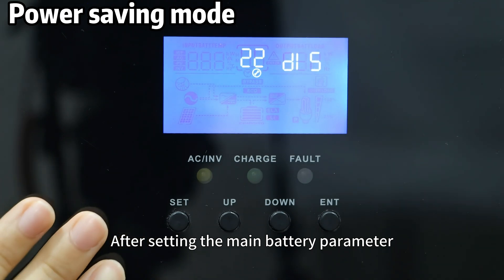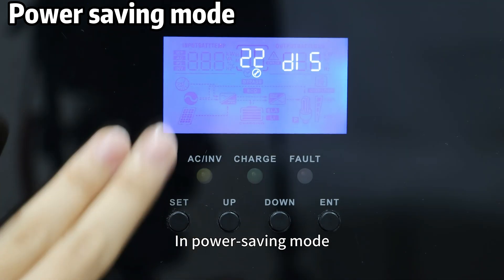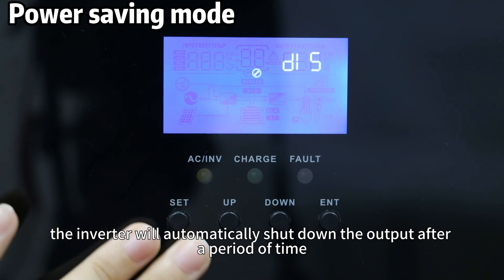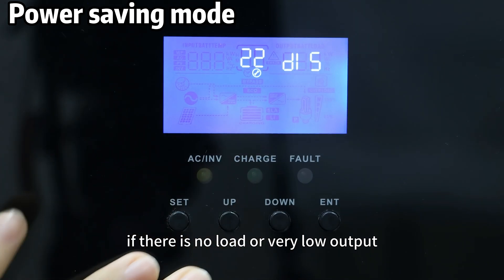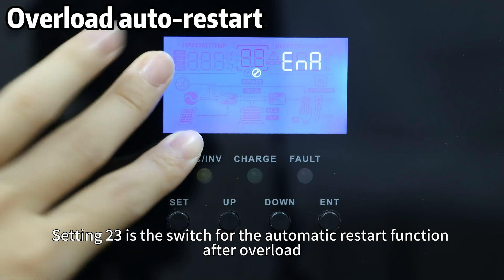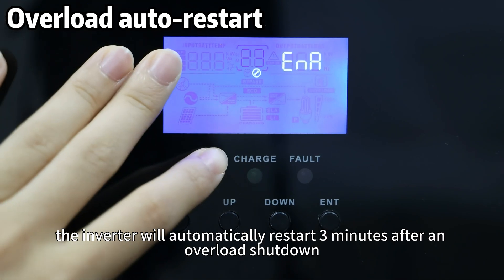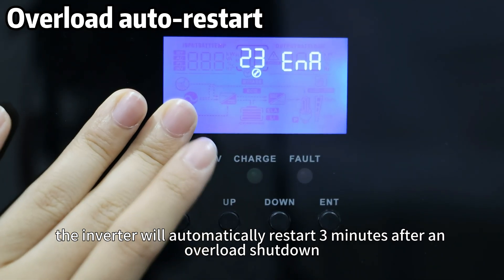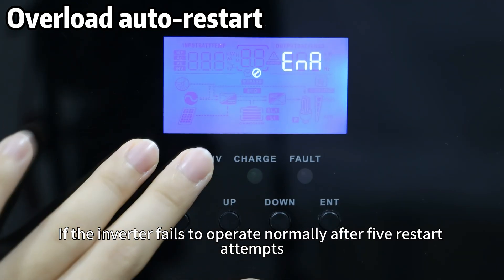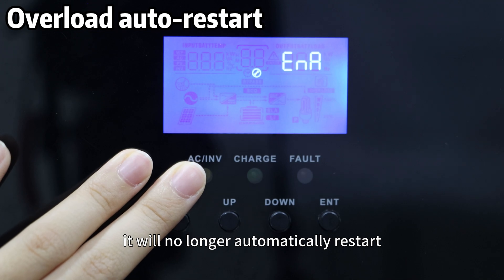After setting the main battery parameters, Setting 22 is used to enable the power saving mode. In power saving mode, the inverter will automatically shut down the output after a period of time if there is no load or very low output. Setting 23 is the switch for the automatic restart function after overload. When enabled, the inverter will automatically restart 3 minutes after an overload shutdown. If the inverter fails to operate normally after 5 restart attempts, it will no longer automatically restart.